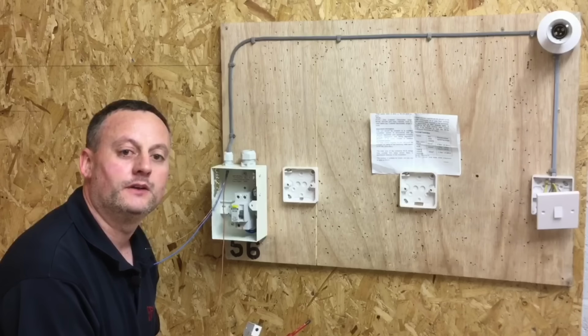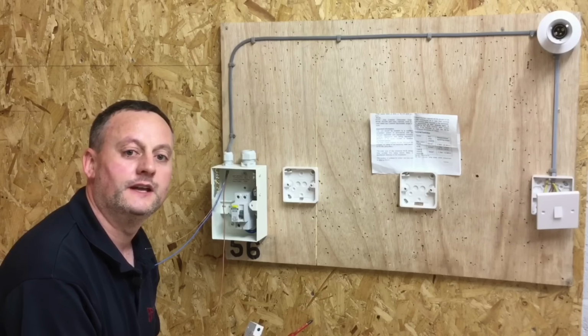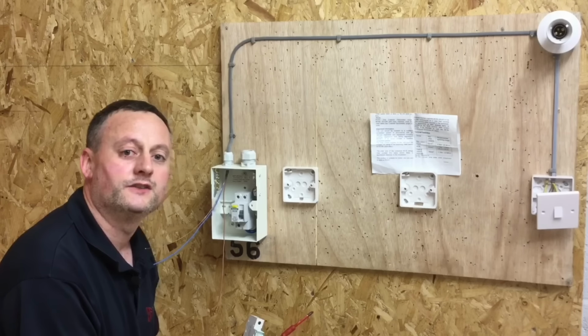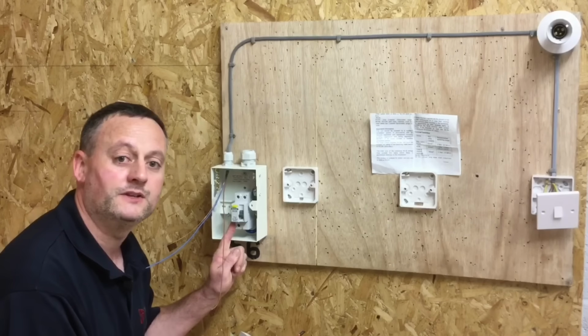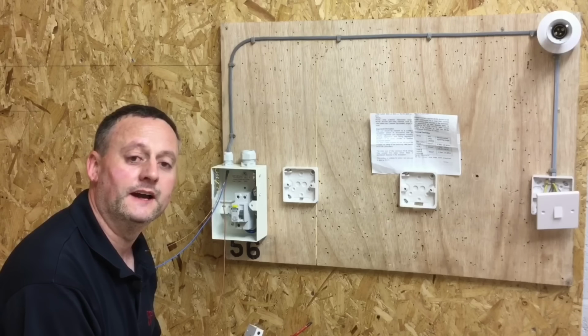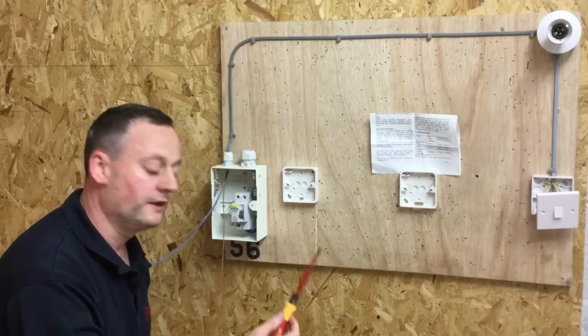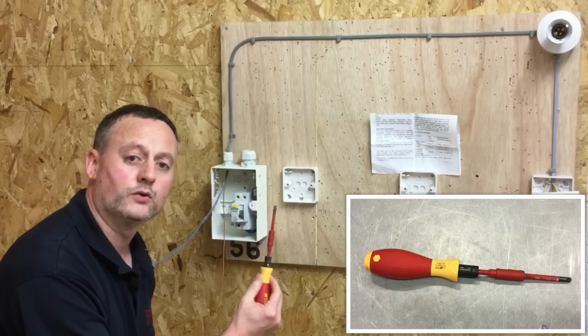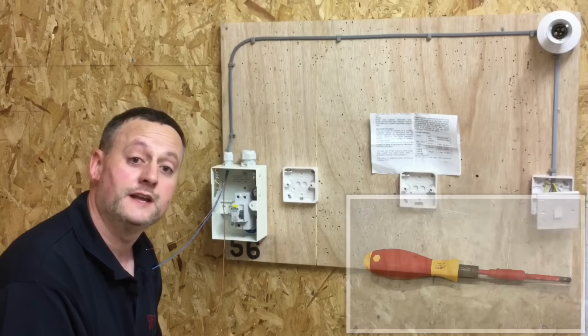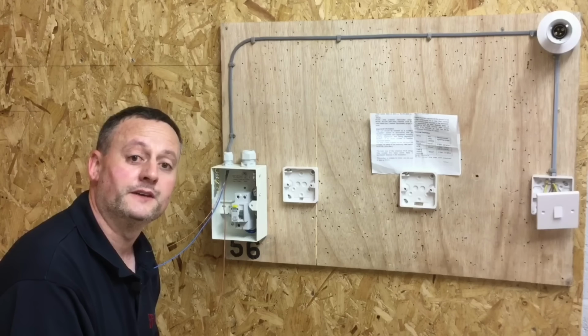So in this presentation, we're going to look at making the final connections for our lighting circuit inside the two-way distribution board. We're going to identify the line, neutral and CPC conductors as circuit number 1, nearest the main switch. There is no secondary circuit in here. We're also going to terminate the conductors and tighten them up with our torque screwdriver to the required Newton meters of torque for both the circuit breaker and the neutral and earth bars.